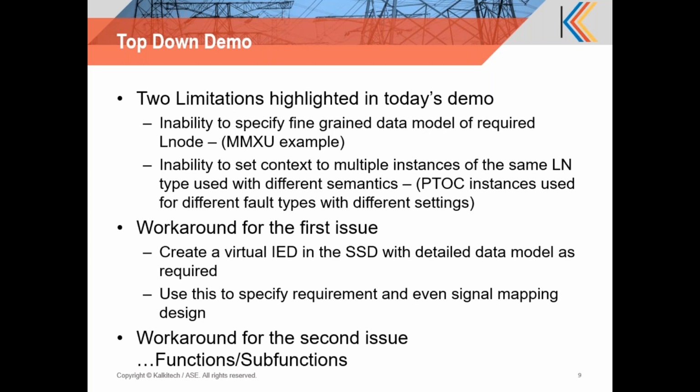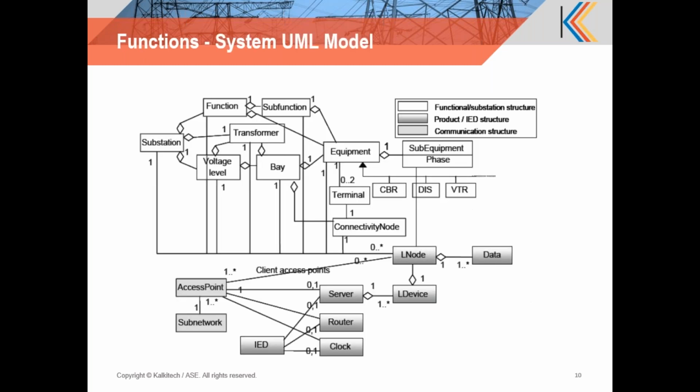The workaround for the first issue is to create a virtual IED in the SSD with the detailed data model as required, and if necessary, go ahead and perform the design as well. In the requirement, you could even provide detailed data sets, reports, and signal mappings between IEDs, if you have created virtual IEDs or dummy IEDs, or ISDs, which is the formal term that is appearing. It's not yet standardized, but once it is, you can use those. In which case, you could do a lot of pre-design or recommended design in the specification itself. The workaround for the second issue, the inability to set context to multiple instances, is functions and subfunctions.